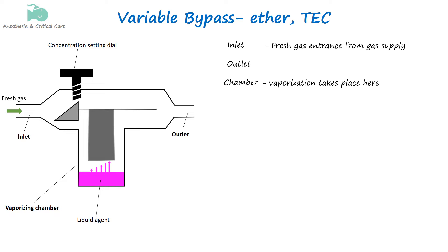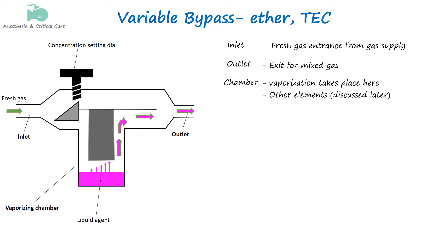The vaporizing chamber features a heating element to assist in vaporization and is designed to maximize contact between the liquid and gas, ensuring efficient vaporization. The outlet is where the vaporized anesthetic mixed with carrier gases exits the vaporizer.